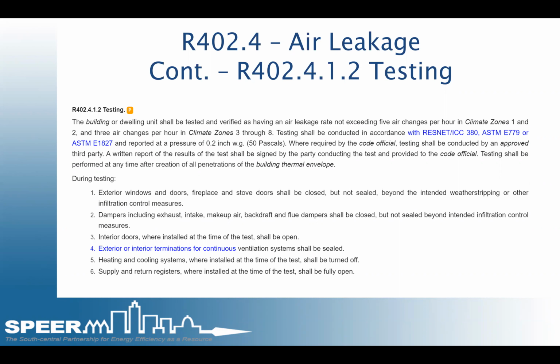The listing here also shows things that can or cannot be done. Exterior windows and doors, fireplaces, and stove doors shall be closed but not sealed. Dampers, including exhaust, intake, makeup air, and backdraft flue dampers, should be closed but not sealed. Interior doors, if installed, must be open. Exterior and interior terminations for continuous ventilation shall be sealed. Heating and cooling systems, if installed at the time of the test, shall be turned off. And all supply and return registers installed at the time of the test should be left fully open.